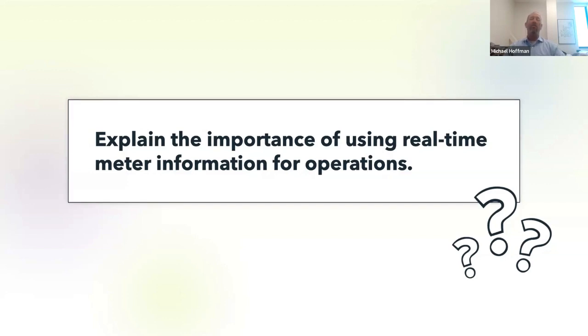So if we set a new peak - for example, here at the university we have two cogeneration systems and self-generate about 42% of our load. The real value isn't in the consumption, it's in managing our demand. We also have one of the largest ice-based thermal energy storage systems in the country, which we use to control our peak.